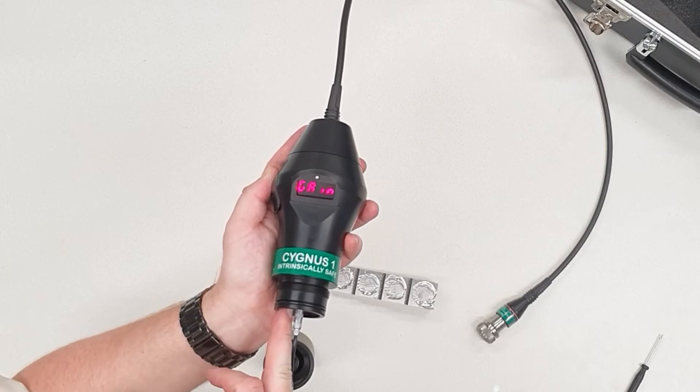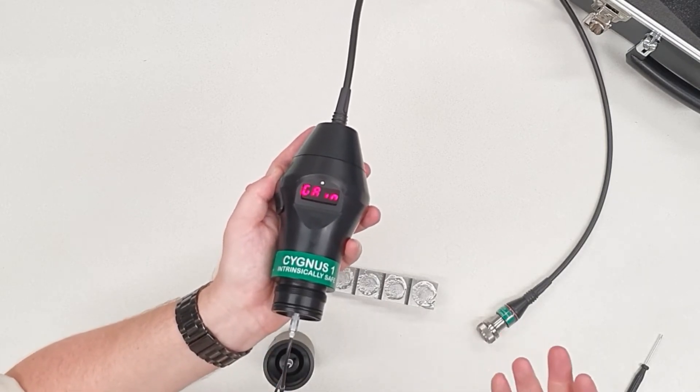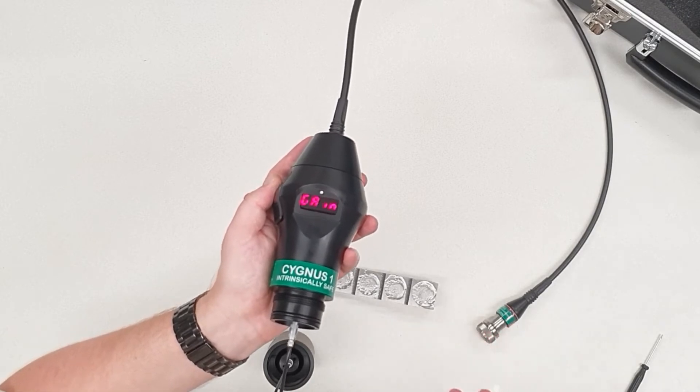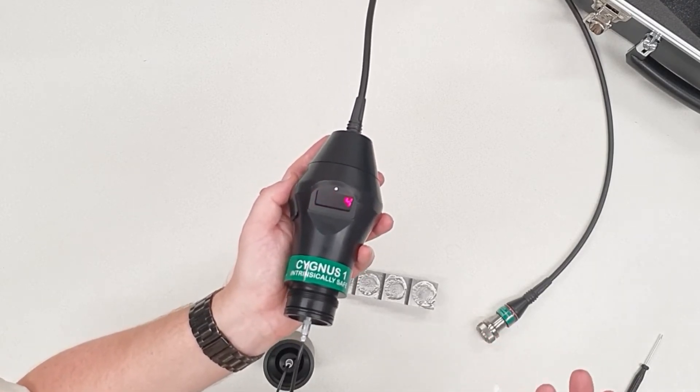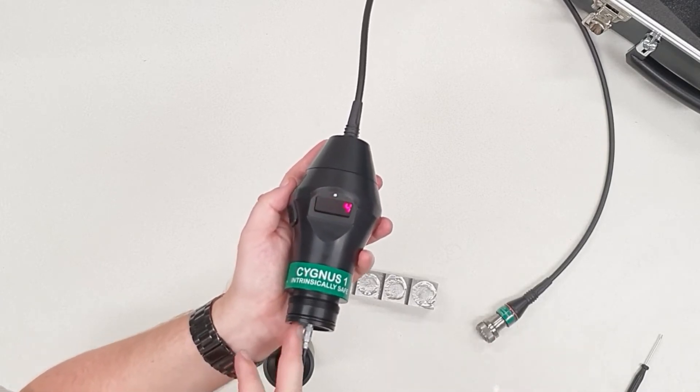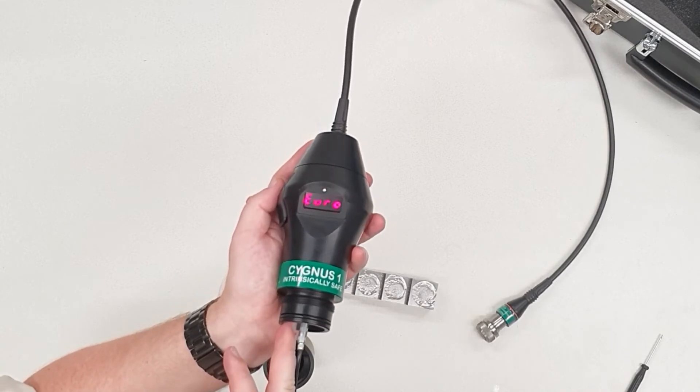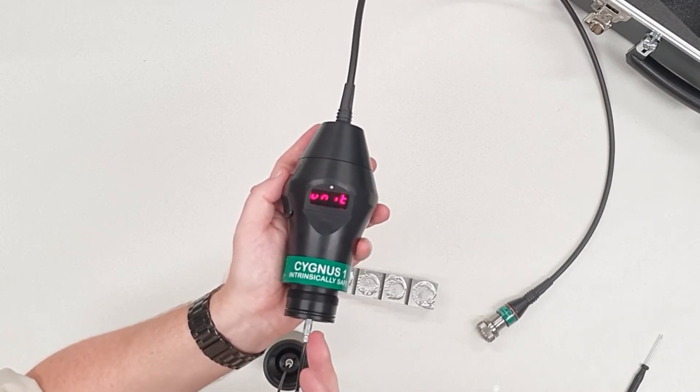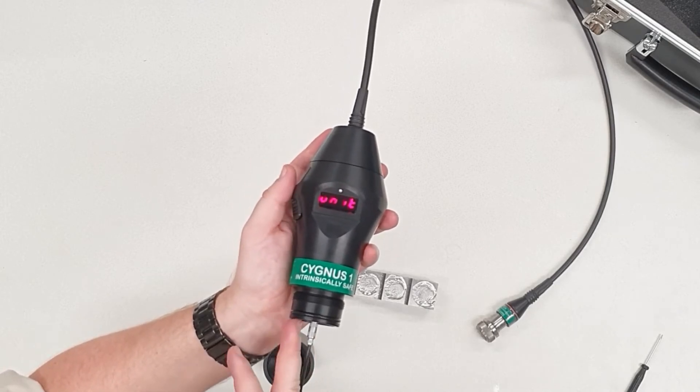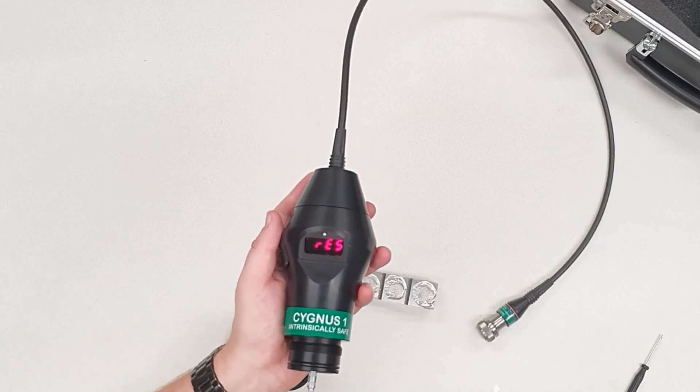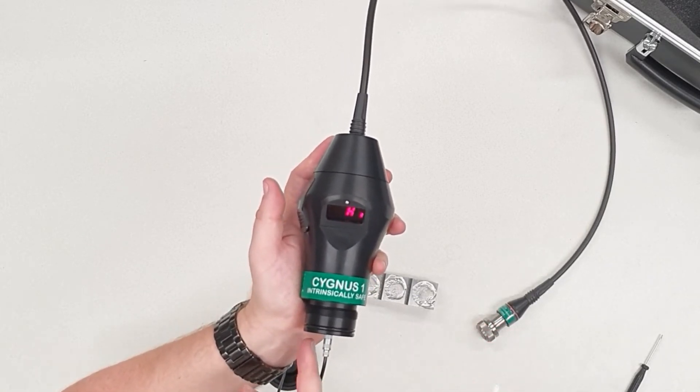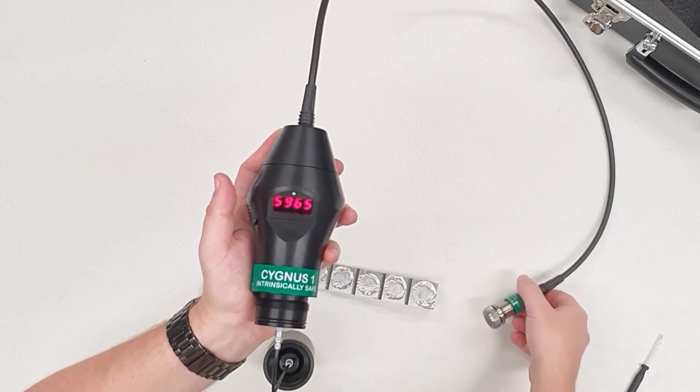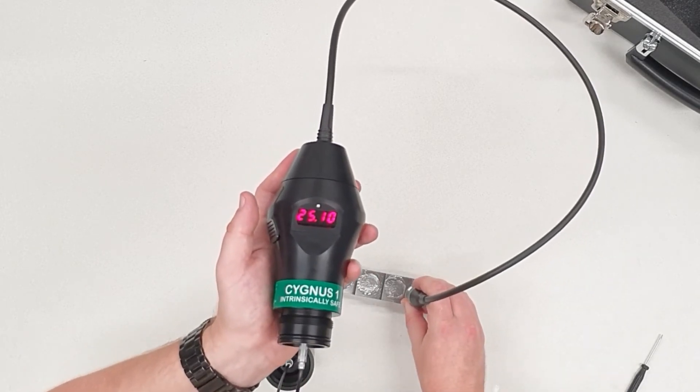Pressing the button underneath again puts it into gain. That's almost like volume control. If you have a probe not working properly, you can turn up the gain to increase the signal, but it's not something I recommend as it can give false readings. You can change the units. It's currently set to euro or metric. You can also change it to imperial. And low res means it's doing it to one decimal place as opposed to two. Change it to high res for two decimal places on your readings.